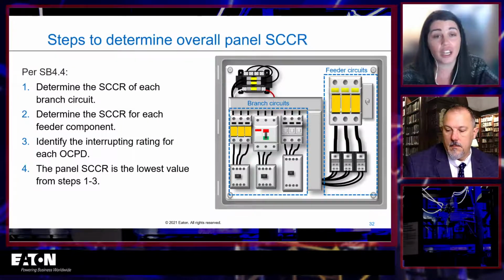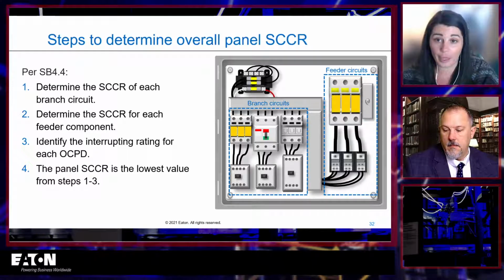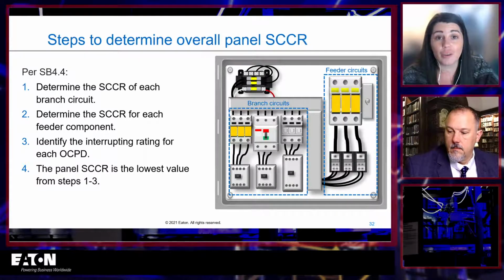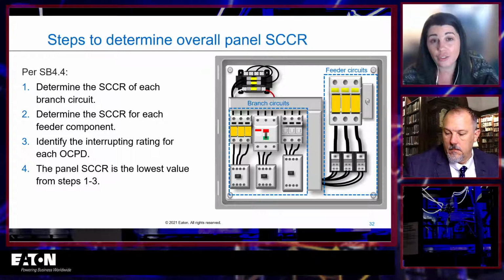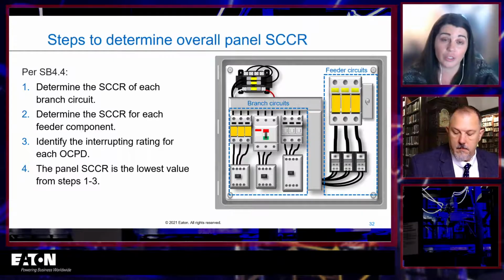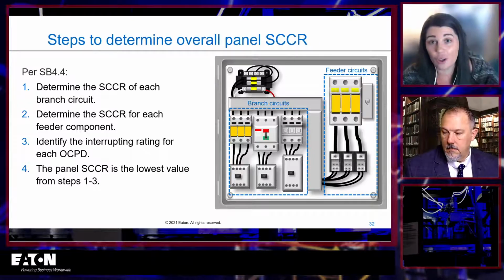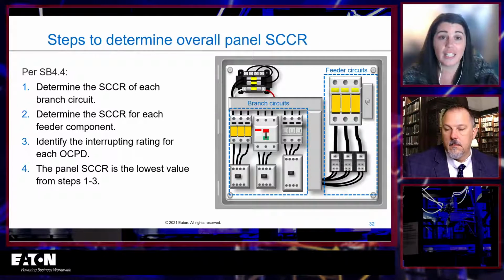So with that, generally speaking, my steps to determine the overall panel short circuit current rating per UL 508A Supplement SB, there are 4 steps. The first is to determine the SCCR for each branch circuit. Step 2 is determine the SCCR for each feeder component. Step 3, identify all of my interrupting ratings within the panel. And then step 4, pick the lowest value from steps 1 through 3, and that is your panel short circuit current rating. So you can see how this is absolutely dependent on those ratings of the devices inside.